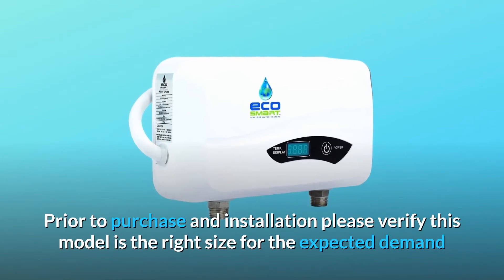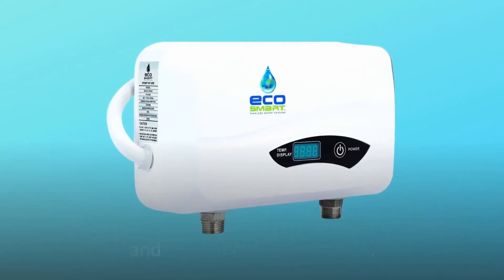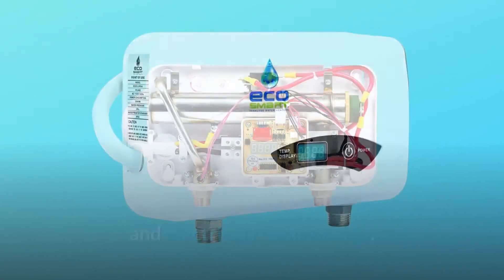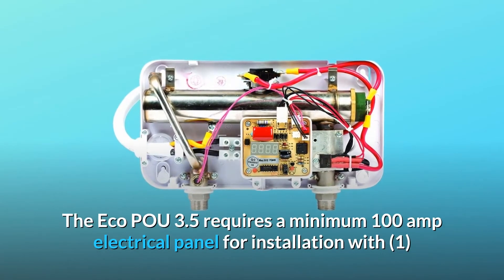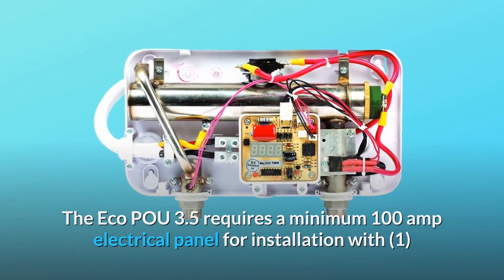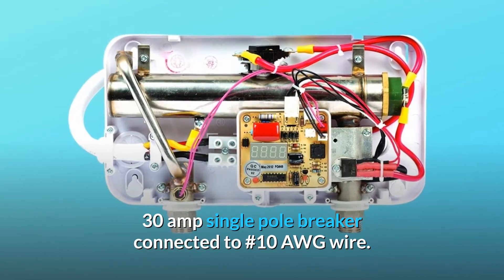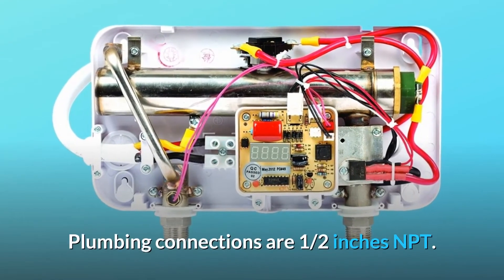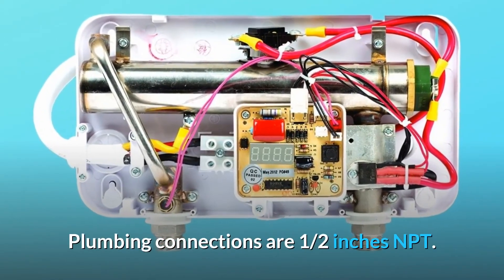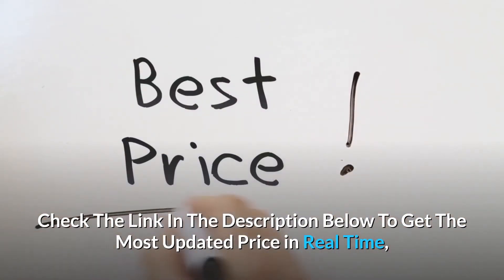Prior to purchase and installation, please verify this model is the right size for the expected demand and electrical requirements. The ECO 3.5 requires a minimum 100-amp electrical panel for installation, with one 30-amp single-pole breaker connected to #10 AWG wire. Plumbing connections are 1/2-inch NPT.